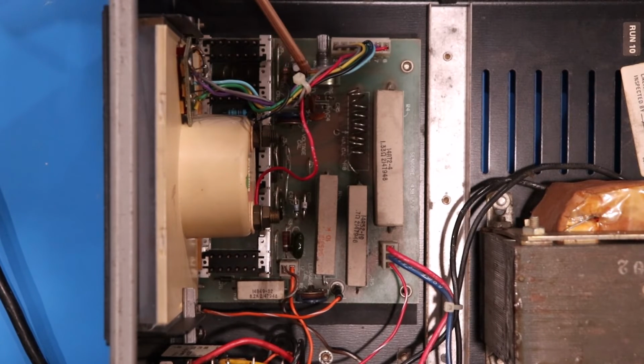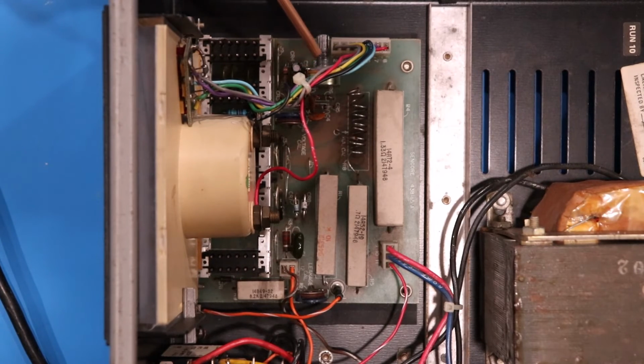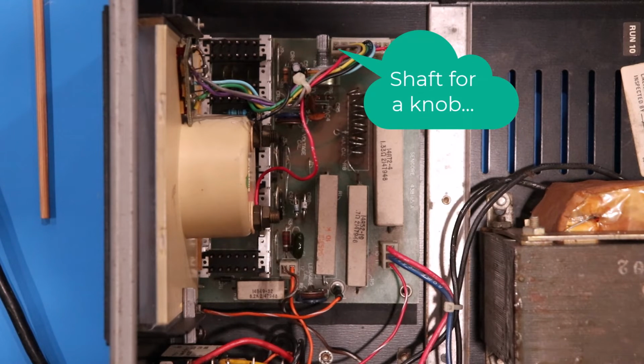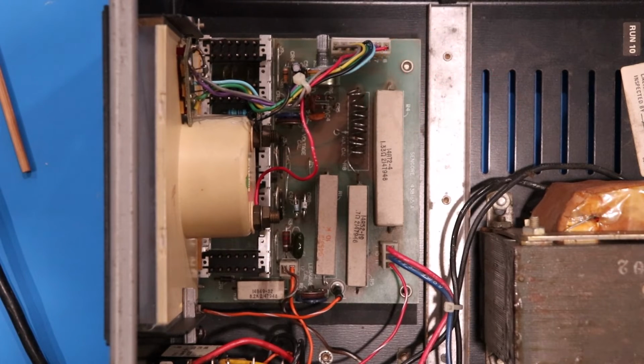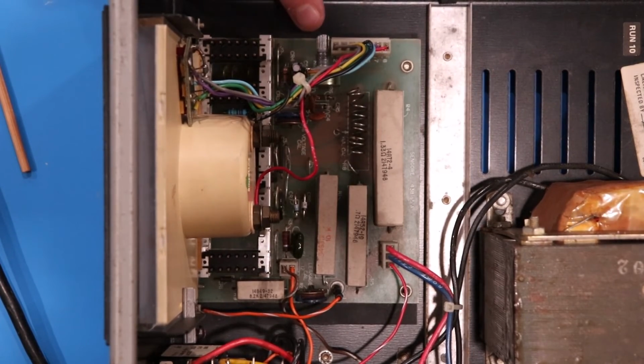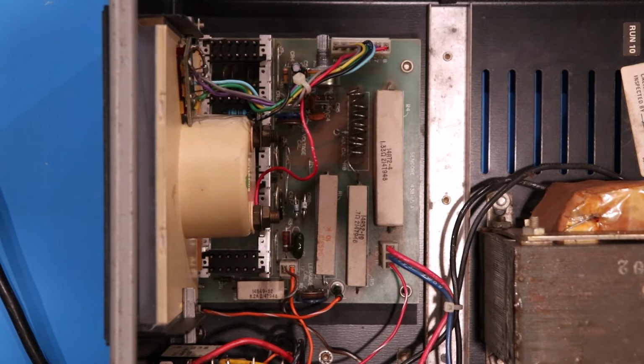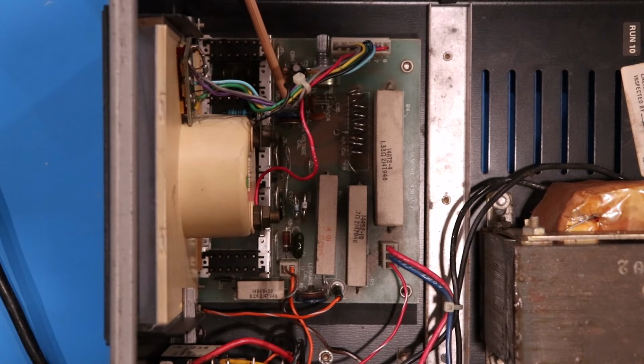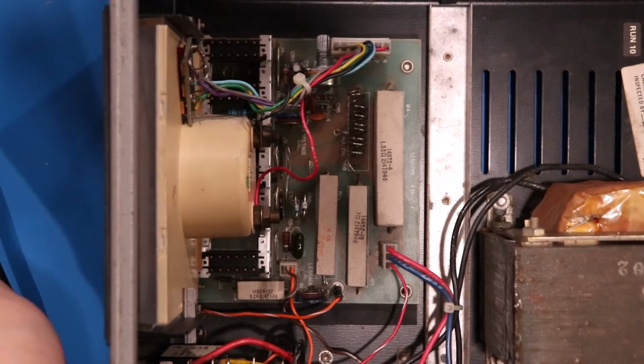So I ended up replacing it, and I did not have an exact same fit, so I had to do just a slight bit of modification, but I ended up replacing it here with one. And as you can see, it's got a knob on it, and I used a screwdriver to adjust it. And we were able to bring the 1.5 amp current setting back in. By the way, once you do that, you do need to go back and readjust the voltage line calibration, which we did. All right. Then, fortunately, fingers crossed here, the 4 amp was actually in spec. So did not have to calibrate it at all.